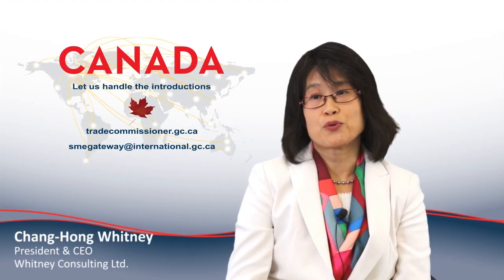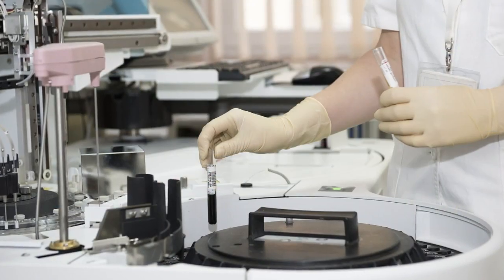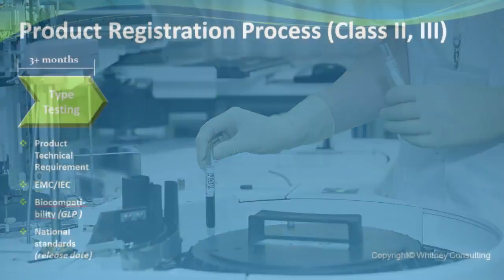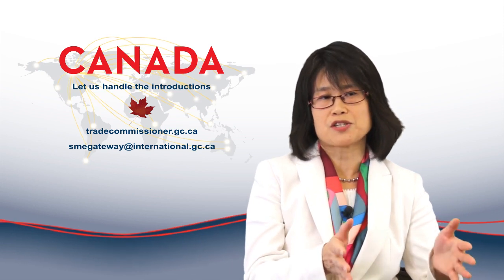For Class 2 and Class 3 products, however, the registration process is a lot lengthier and more costly. These products require product testing in China, done at CFDA-authorized testing centers. The purpose is to validate product safety, effectiveness, and performance. Testing can be pretty lengthy — sometimes two to three months, and if there are issues, four to five months — with extensive discussions between testing engineers and the manufacturers.